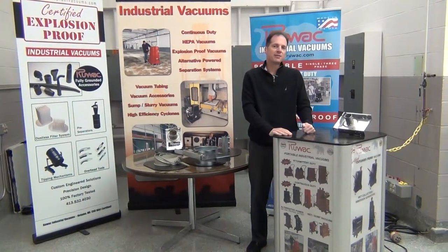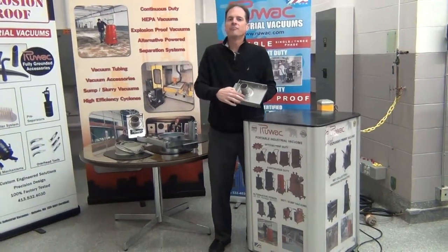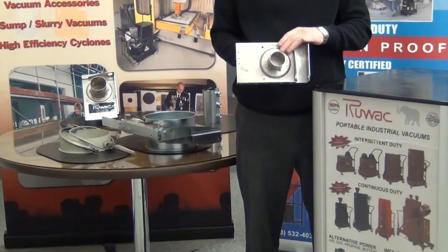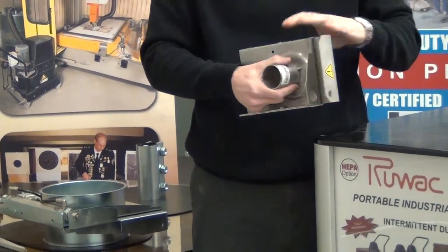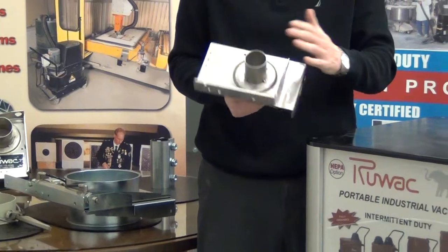Today we're reviewing Ruwac pneumatic blast gates and manual blast gates that are airtight. These blast gates are unique in that they have a fully gasketed area on both sides of the blast gate that allow it to be airtight from outside air. You won't get any leakage from the outside of the valve and you also won't get any leakage across the valve when the valve is shut. You can use these for vacuum systems up to 16 inches of mercury and be completely airtight.